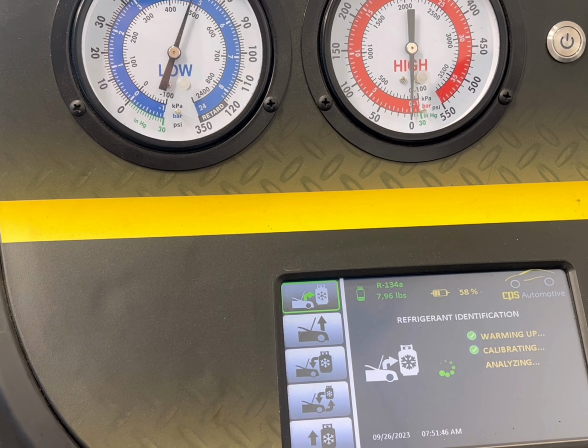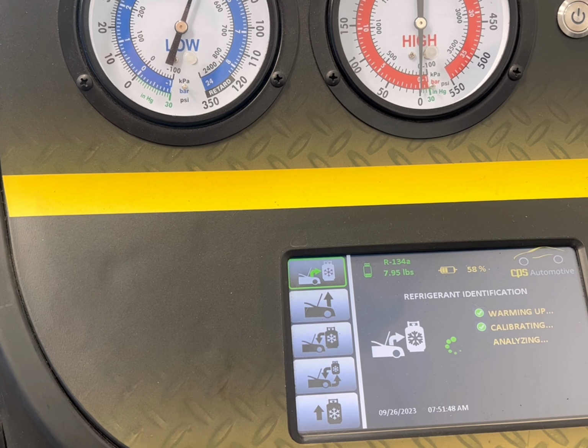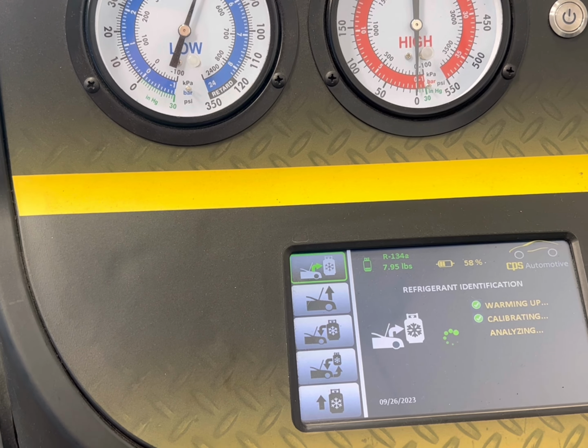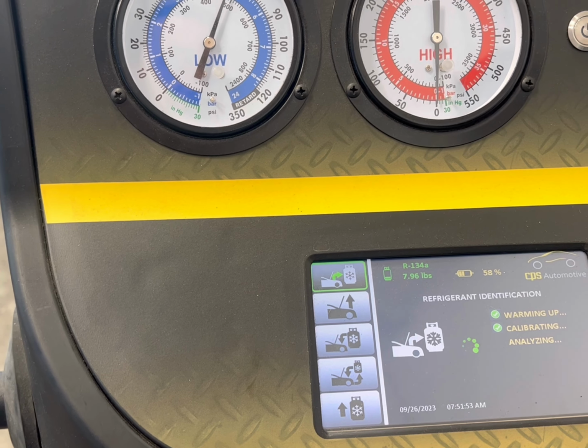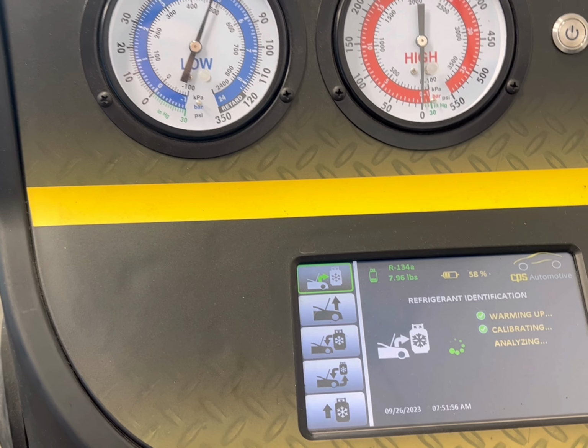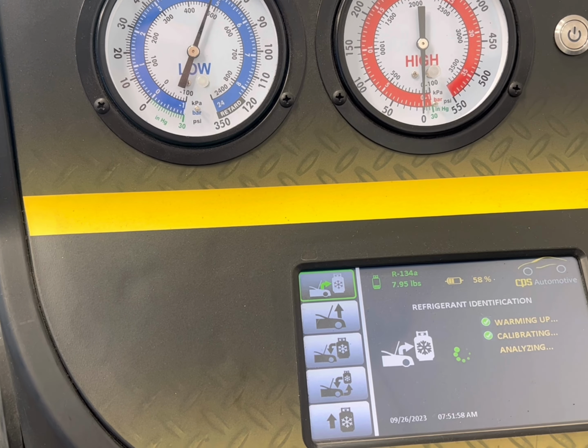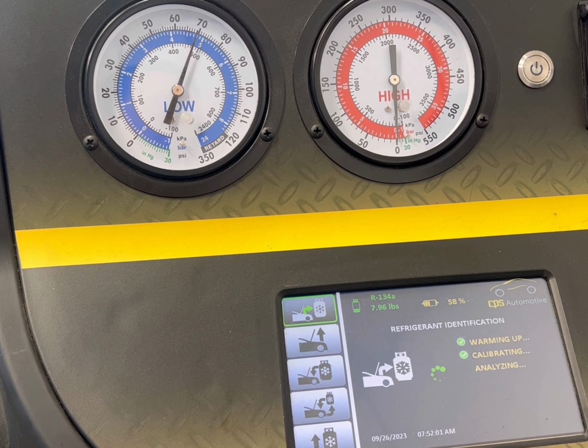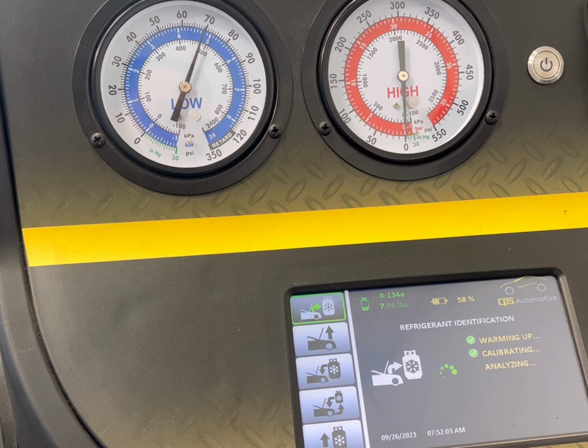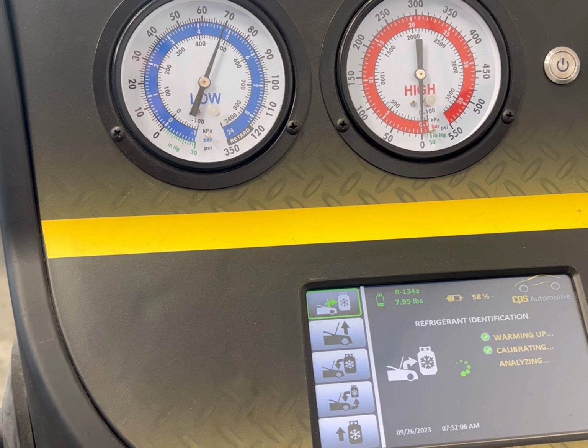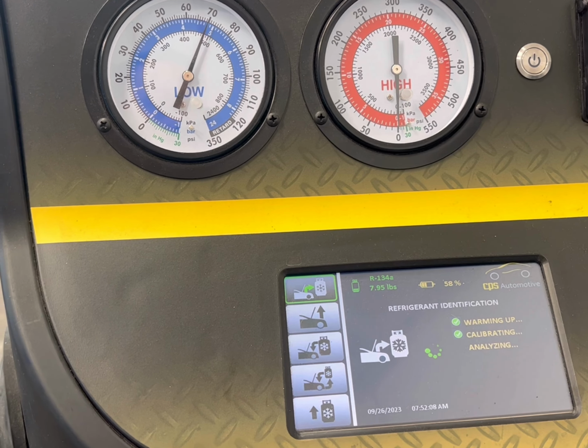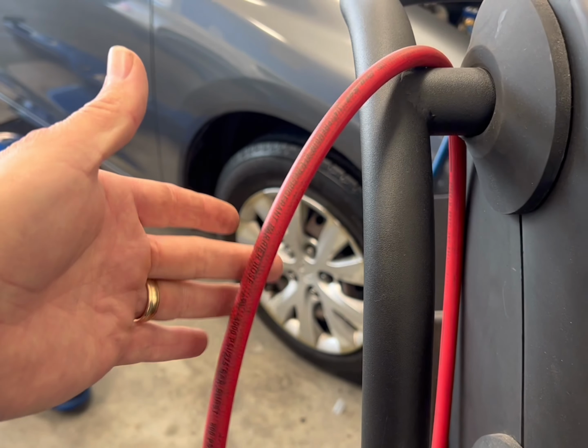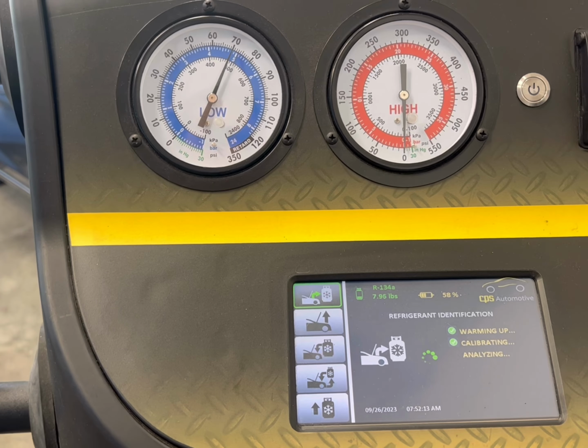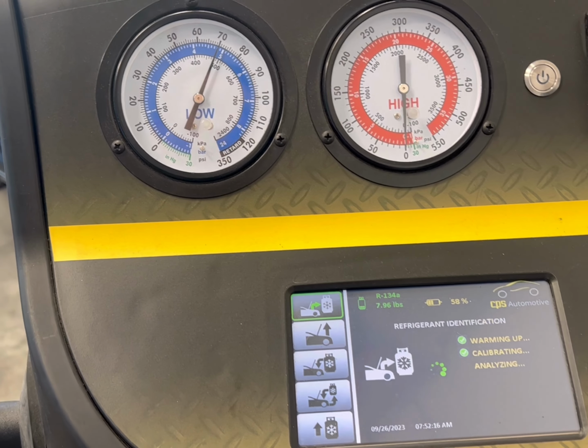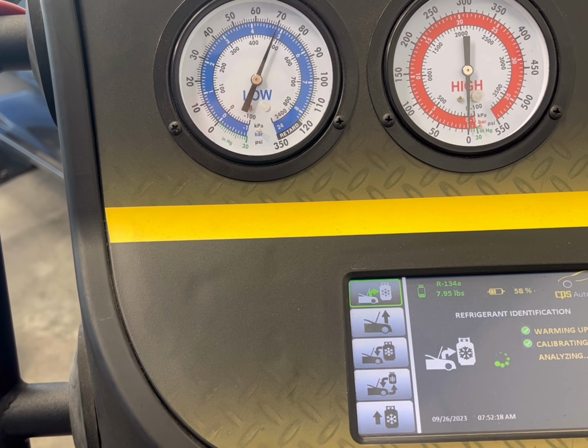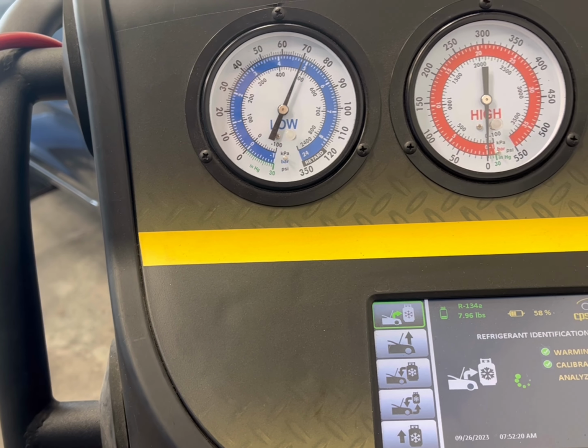If it passes, it'll show R134 and any kind of percentage of air that might be in the system. If there's air in the system, that's usually due to prior maintenance that had air injected in there accidentally. That could happen because someone injected oil and didn't purge the line correctly of all the air, or they recharged it and it purged the air out of the lines. So air doesn't just go in naturally, okay? Or they didn't do a good vacuum and had air trapped in there and recharged it. That could be a possibility too.